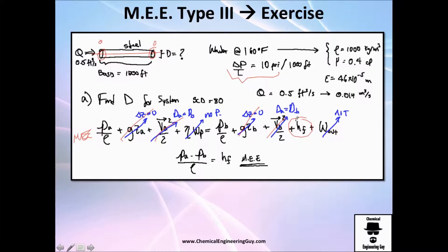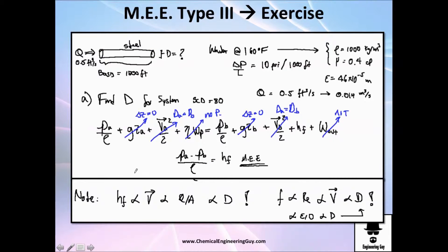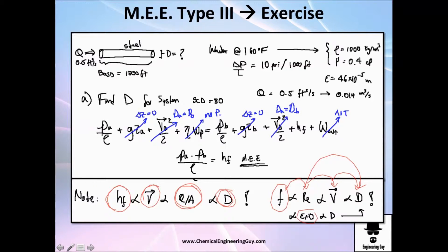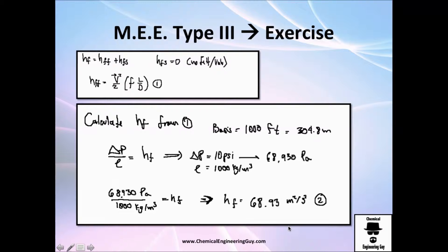We are left with the friction loss and the change in pressure. The friction loss depends on velocity, and velocity needs volumetric flow rate divided by area, which in turn requires the diameter. For the friction factor we need Reynolds number, which depends on velocity and diameter. Reynolds number and relative roughness both depend on diameter — this is the first time relative roughness is a significant factor. There are no fittings, so we only have friction loss due to the pipe wall. By definition, friction loss in a pipe wall is the velocity head multiplied by the friction factor times length divided by diameter — call this equation 1.